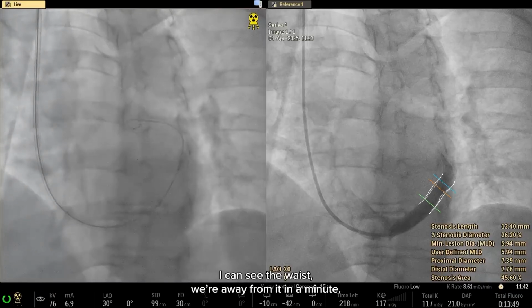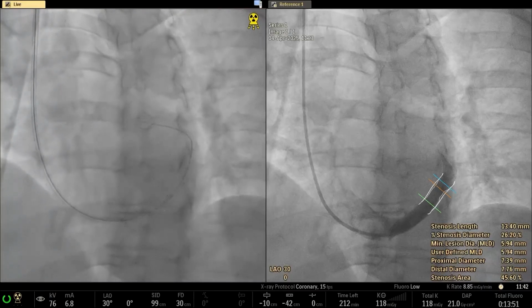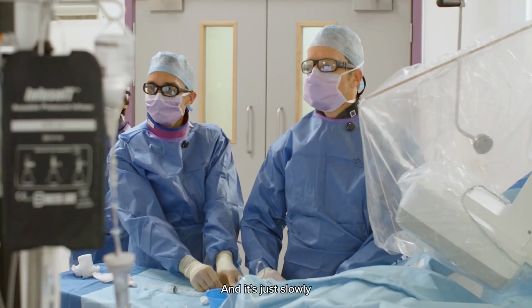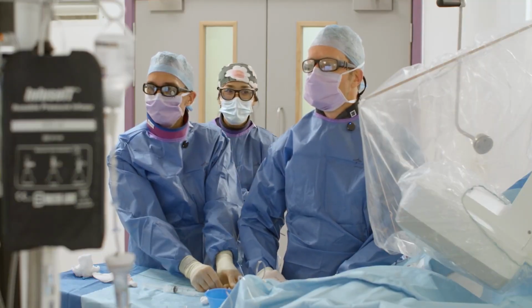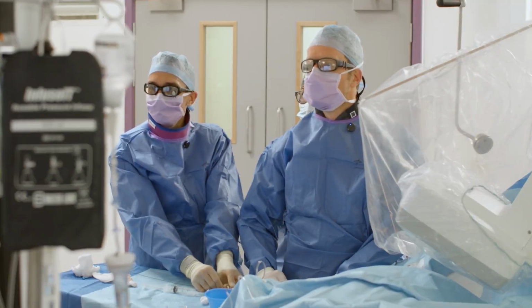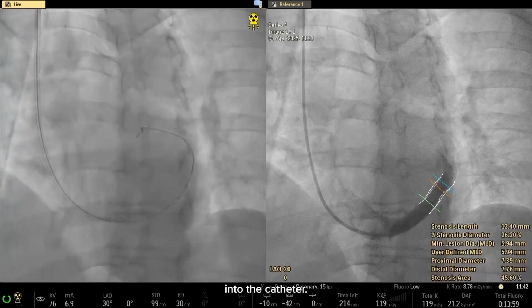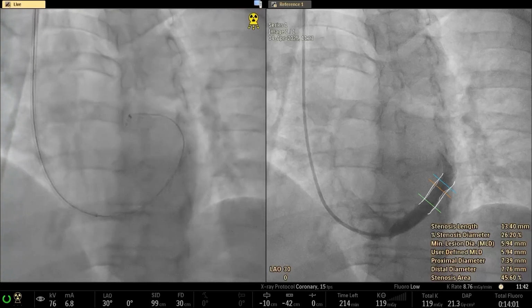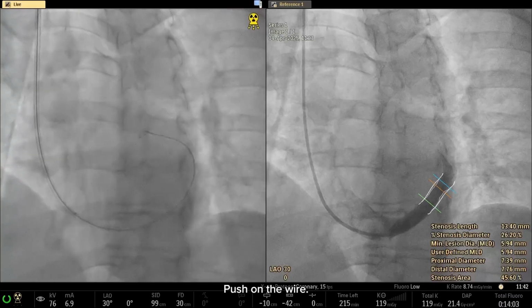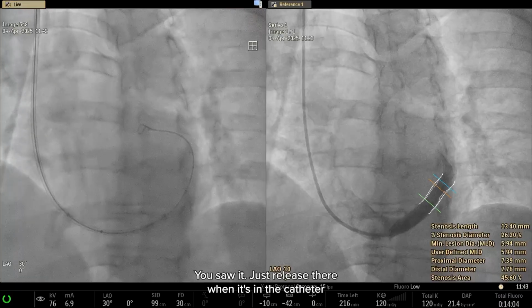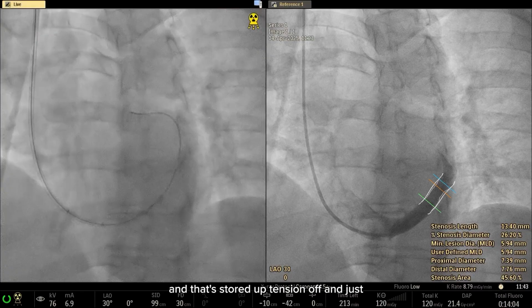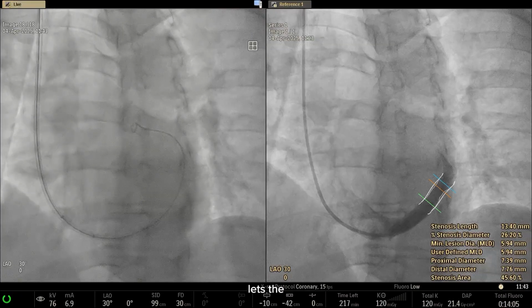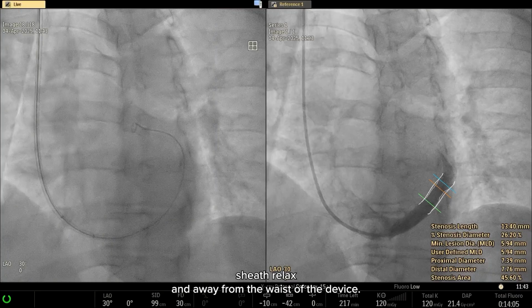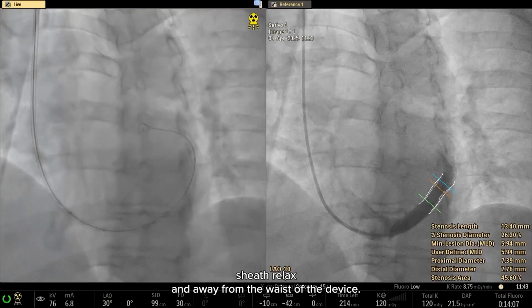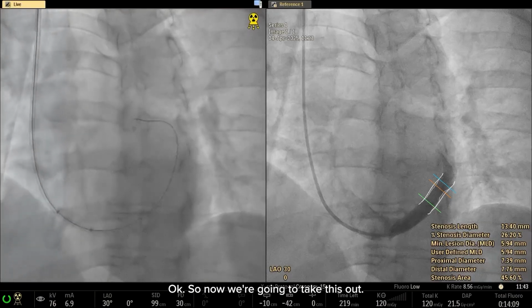I can see the waist, we're away from it at the minute. And it's just slowly bringing that balloon into the catheter. Push on the wire. There we go. You saw it just release there. When it's in the catheter, that stored up tension often just lets the sheath relax and away from the waist of the device.